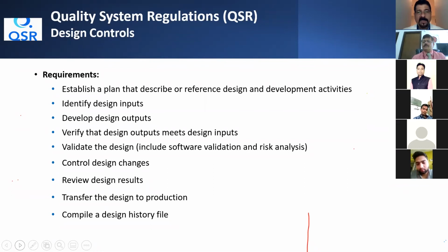So the dimensions, the pictures, the layouts, the designs, all are part of the design output. They are all different terminologies used in this design control. Then you have to verify that those design outputs are meeting the design input. Once you do that, then you validate your design. Whatever you have designed, you have to validate that, including the software. You perform risk assessments and you validate that the design is performing, or that the design is well suited for the specific need for which I have designed this.